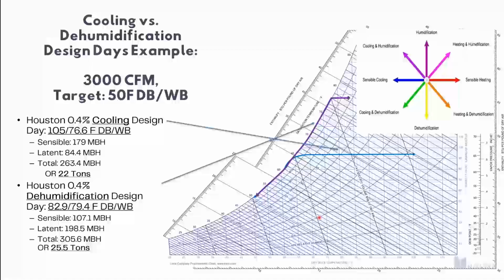And to pull that moisture out of the air, it takes a lot more energy and frankly capacity to do so. This is an example in Houston, where your cooling design day is 105 and 76.6. You have about 22 tons of cooling required to hit a 50-degree off coil. Now, under a dehumidification design day, only 82.9 outside dry bulb, 79.4 wet bulb, you actually need 25.5 tons of capacity. So just to give you an idea of what kind of delta you're looking at if you're only sizing around your cooling design day. Under a dehumidification design day, if you only sized around cooling, you would actually be undersized and not be able to achieve the target condition. So best practice, I would suggest that you look not only at cooling design day, but also dehumidification design day, as that may drive your peak load condition.